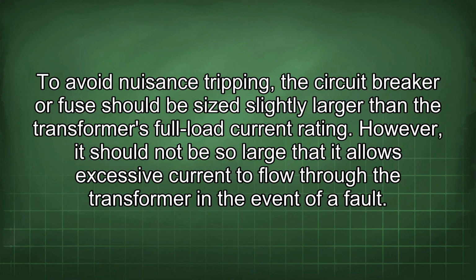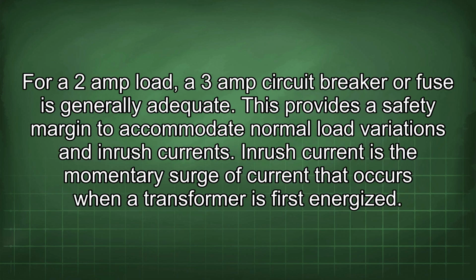To avoid nuisance tripping, the circuit breaker or fuse should be sized slightly larger than the transformer's full load current rating. However, it should not be so large that it allows excessive current to flow through the transformer in the event of a fault. For a 2-amp load, a 3-amp circuit breaker or fuse is generally adequate. This provides a safety margin to accommodate normal load variations and inrush currents.